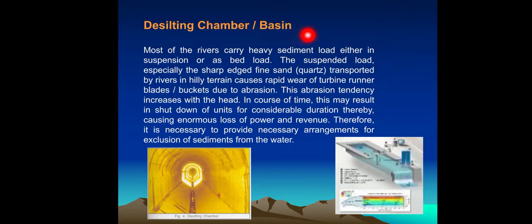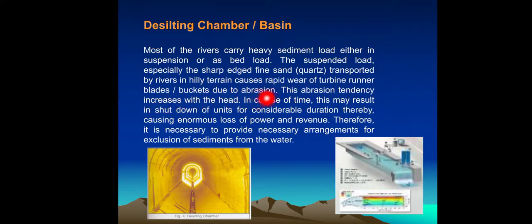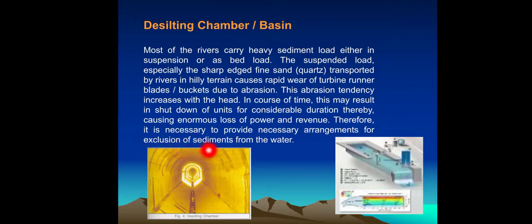Desanding Chamber: Most rivers carry heavy sediment load, either in suspension or as bed load. The suspended load, especially the sharp-edged fine-sand quartz transported by rivers in hilly terrain, causes rapid wear of turbine runner blades and buckets due to abrasion. This abrasion tendency increases with head. In the course of time, this may result in shutdown of units for considerable duration, thereby causing enormous loss of power and revenue. Therefore, it is necessary to provide arrangements for exclusion of sediments from the water.